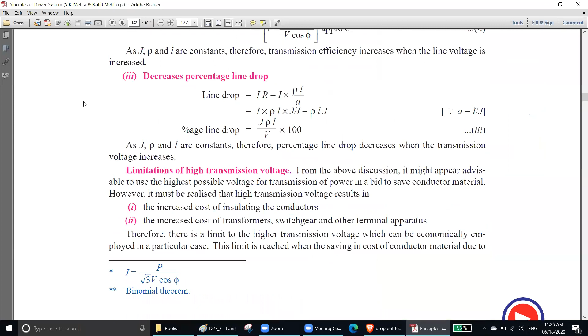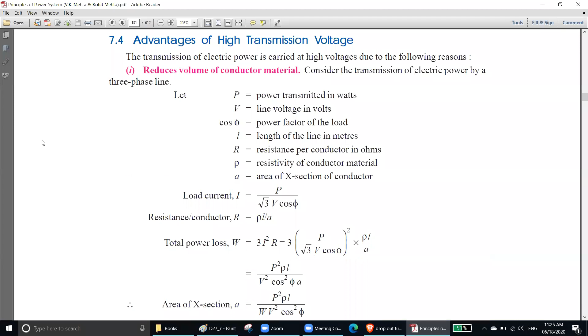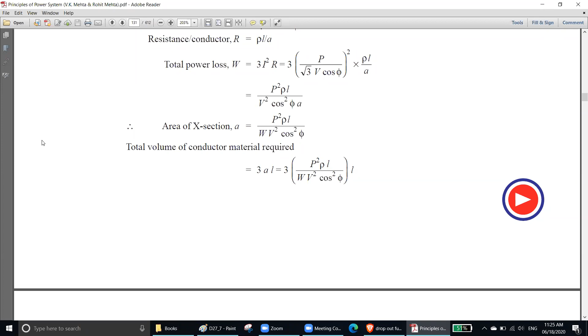Advantages of high transmission voltage: it reduces the volume of conductor material needed. Volume means length into area. Your length is fixed because you cannot move your generating station near to your city. But you can reduce the volume by reducing the area, meaning you can make your conductor thinner.